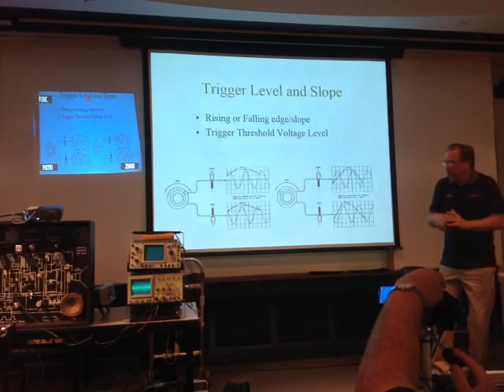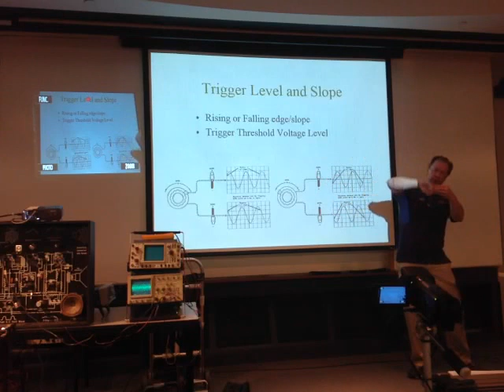So let's talk about the most common controls you're going to use, which are just doing a simple edge trigger, trigger on a rising or falling edge of a signal. Okay, so we're going to trigger when the voltage on that signal comes up through a threshold and then kick off the sweep. Or I'm going to trigger when the signal falls through a threshold and kick off that sweep.